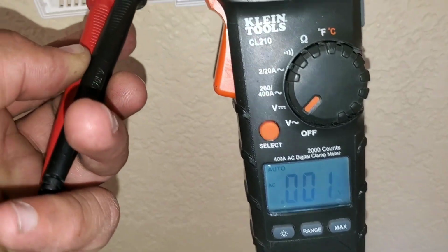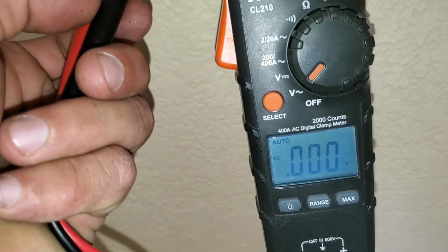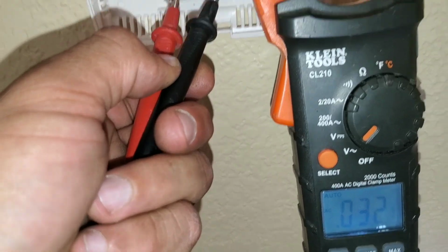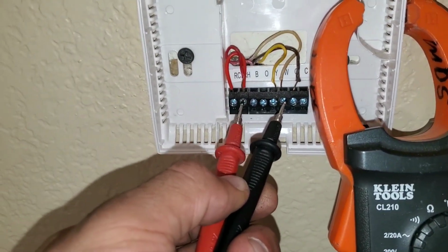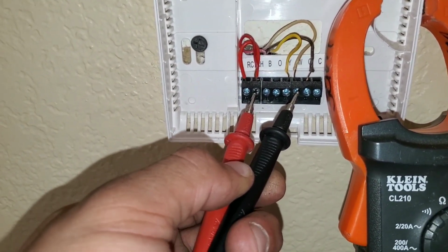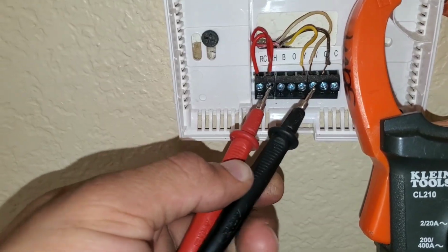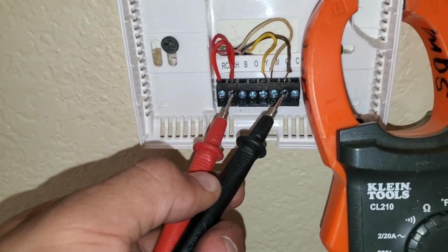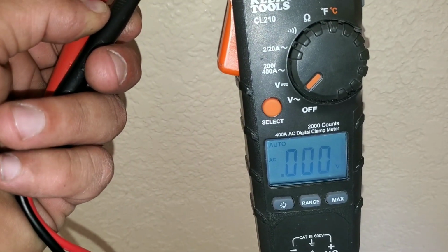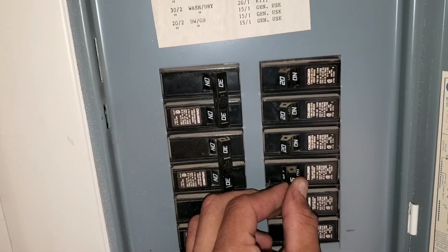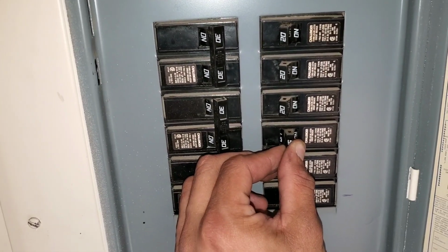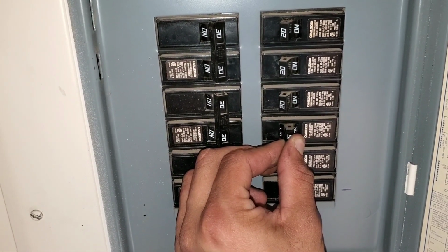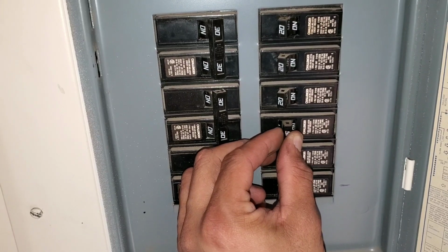So here we have our multimeter set to volts AC, and we're testing each of our terminals. We checked the Y, there was no voltage, the W, and now we're checking our G terminal, and we do not have voltage. You can see here that we do not have voltage because our breaker is tripped. So you want to make sure that you set it to the off position and then turn it back on.